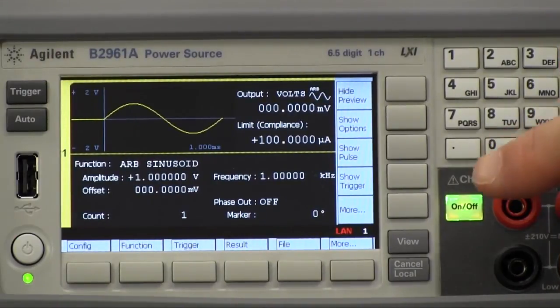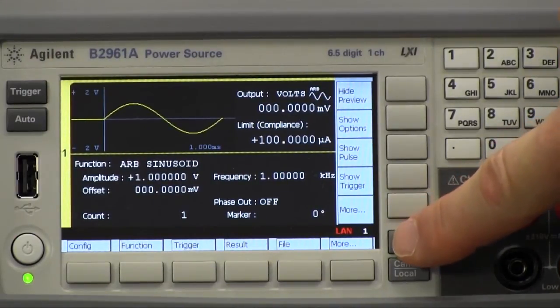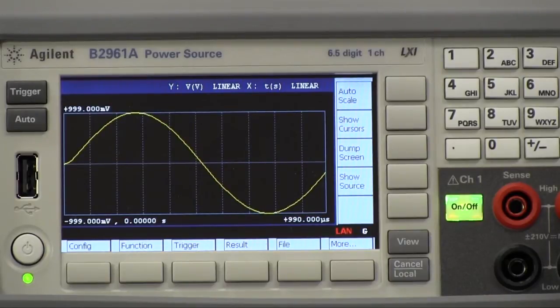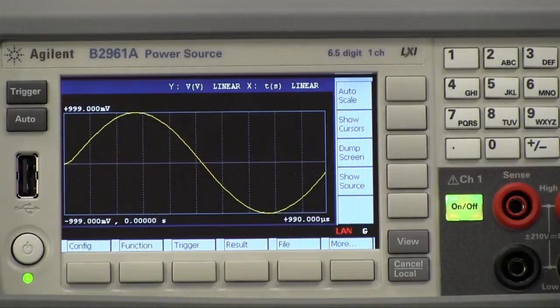And now notice that by going to the view mode, I can also show you the voltage sinusoidal waveform we've just applied also on the front panel of this instrument. And this is not a preview, this is actual measurement of the waveform we've just applied.